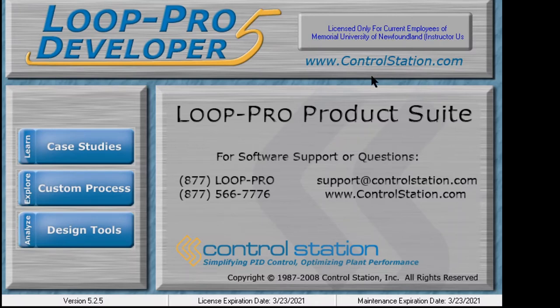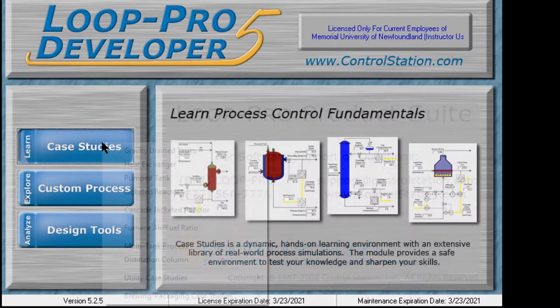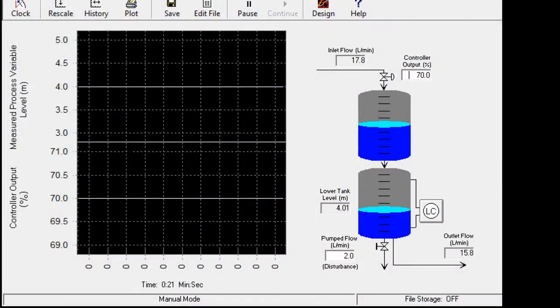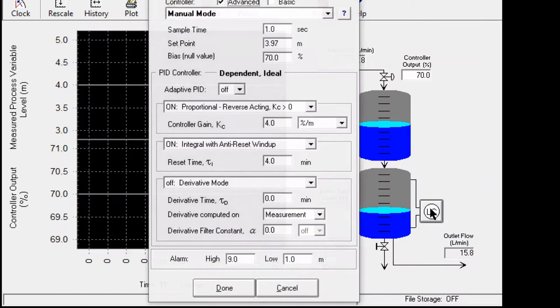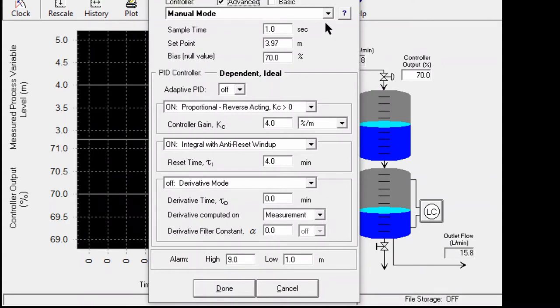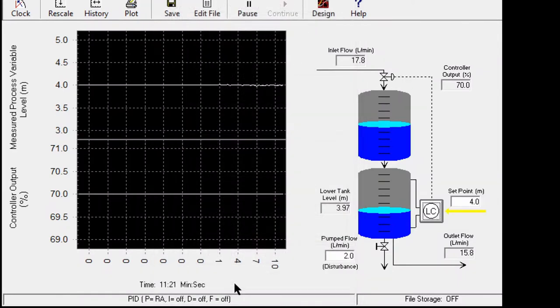Let's look at the continuous cycling method using the example of the gravity drain tank process. For this case, as the procedure suggests, we need to put the controller with a proportional only controller, meaning you turn off the integral mode and the derivative mode, and then make a small increase in the setpoint.